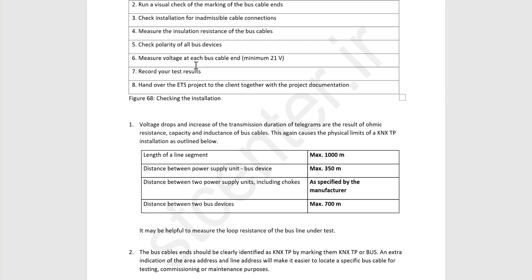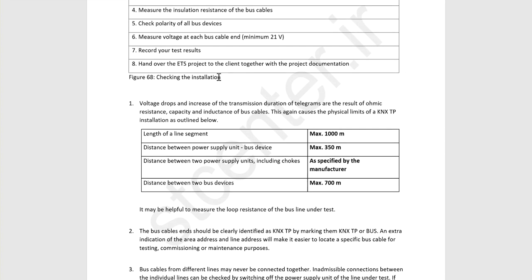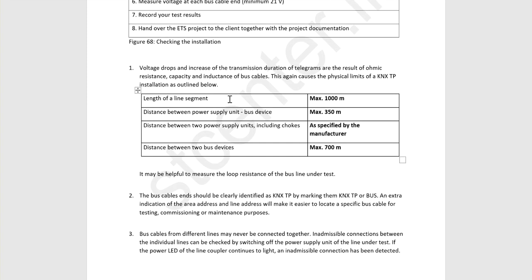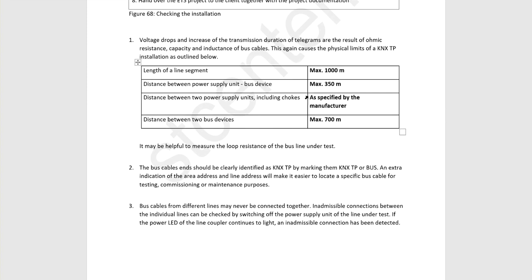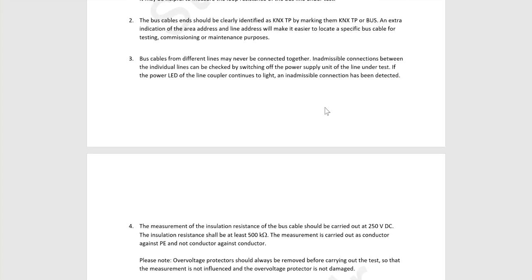Check the polarity. Always you should check the polarity and make sure that red goes with red and black with black. Measure the voltage at each bus cable end. You should have minimum 21 volt DC in the furthest devices. Record your test. You should record your test and hand over the ETS project to the client. Remember that. And always you should keep in mind these distances: 1000 meter, 350 meter, 700 meter, and so on.